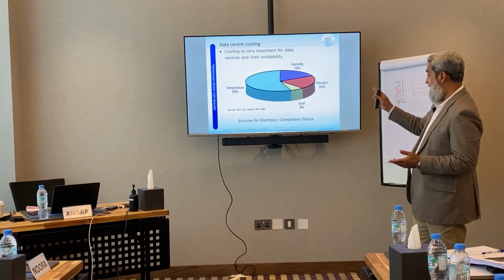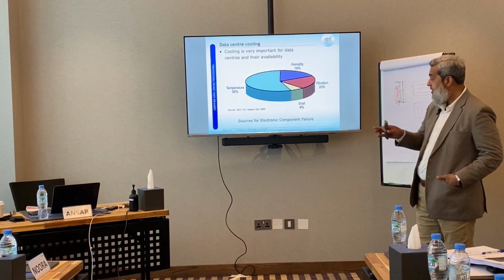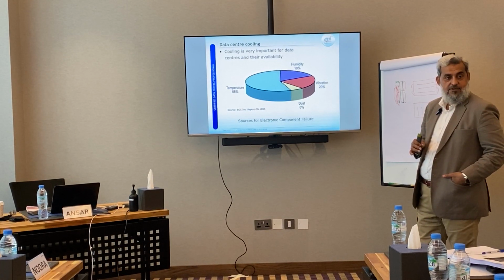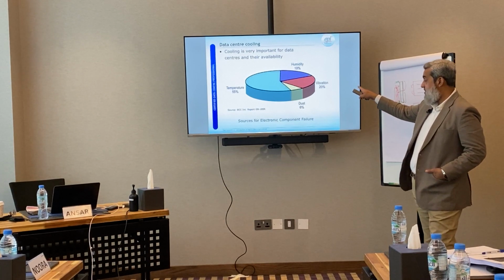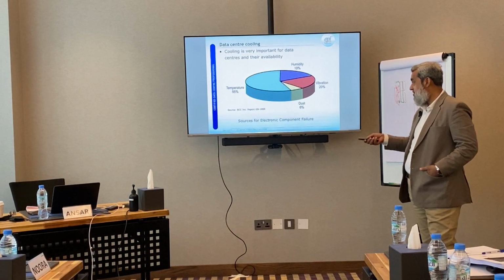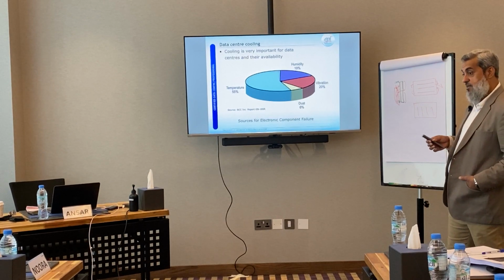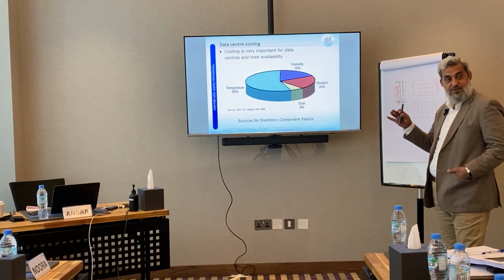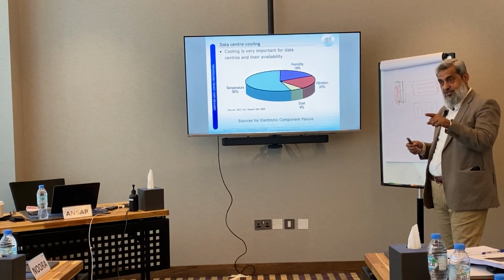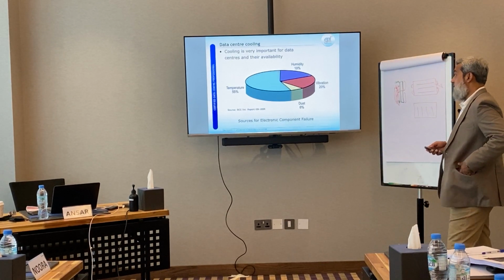As per the international research, 55% of the equipment which fails in the data center fails because of high temperature. 20% is vibration. 19% is humidity, and then contamination and dust is 6%. So we should be careful about the environment, like the right amount of airflow, temperature, humidity, no vibration. We discussed yesterday creating a gap with the raised floor and protecting from the vibration and all.